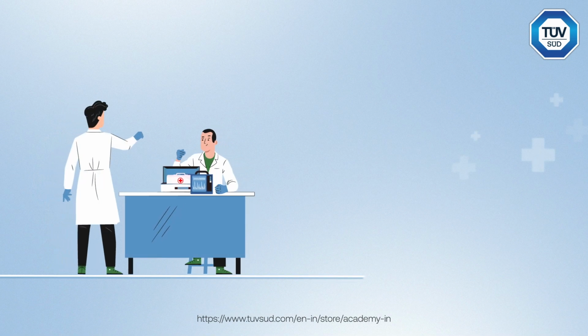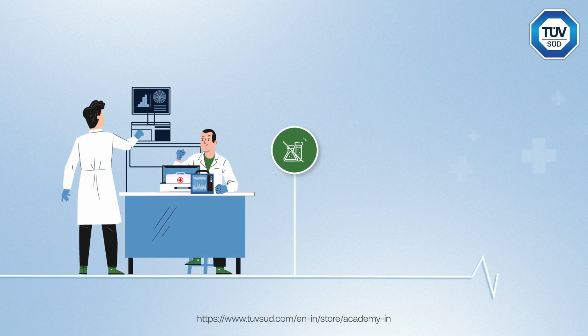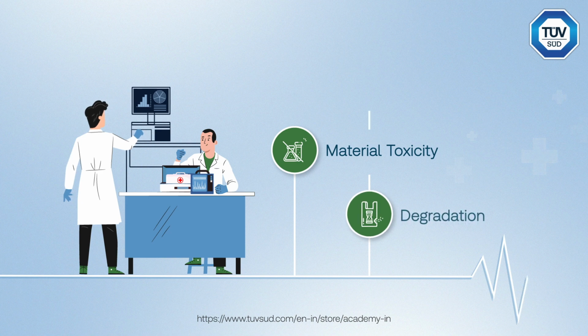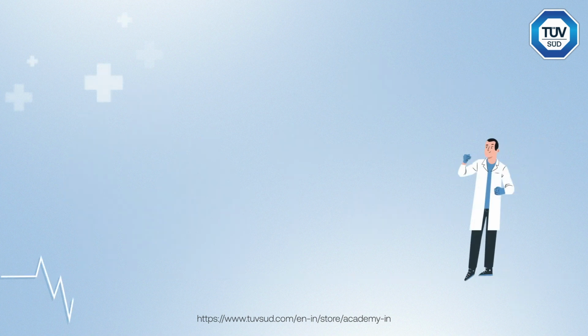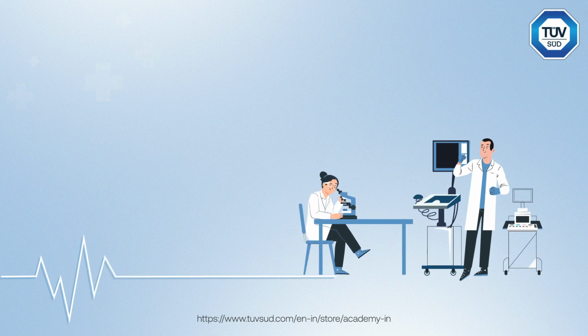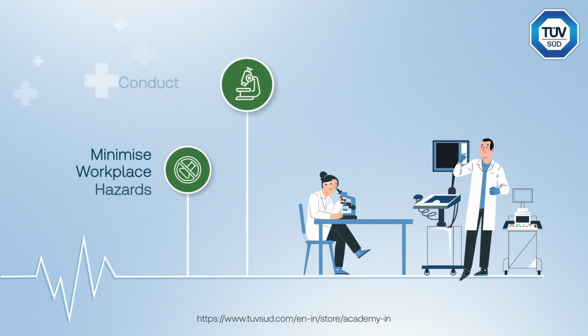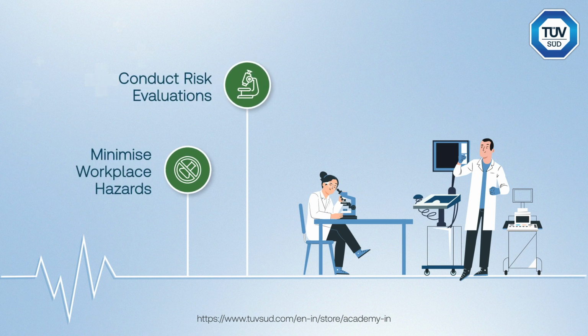Toxicity risk assessment in medical devices is crucial to avoid critical risks, like material toxicity, degradation, and biological risks. ISO 10993, Part 1, specifies requirements of toxicology risk assessment to minimize workplace hazards and conduct risk evaluations.